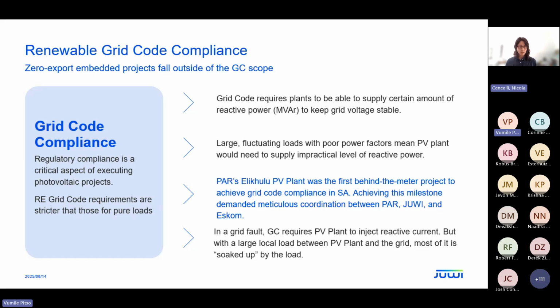It's quite tough, but we managed through extensive engagement with Eskom, and you'll see there are many more behind-the-meter projects which are happily grid code compliant, except for a few exceptions. I did want to note, though, that this is changing - with the inclusion of BESS, or battery energy storage systems, they can provide a lot of the reactive power compensation needed, as a fast response. So we're finding it's much easier to smooth grid disturbances for the load, and much easier to obtain grid code compliance when we have a co-located BESS system.